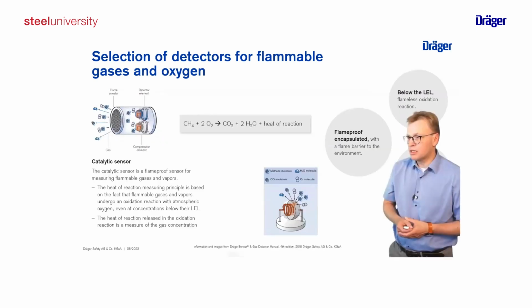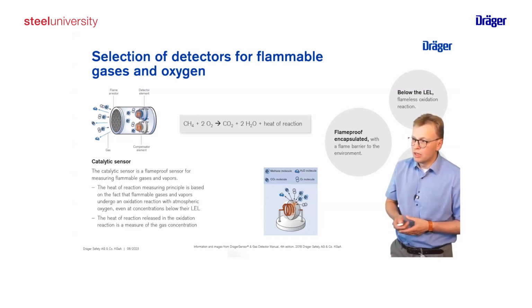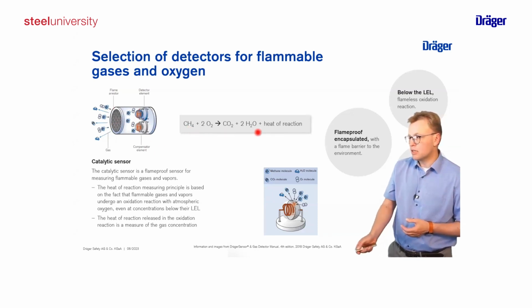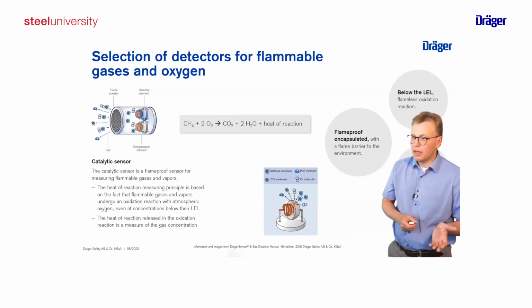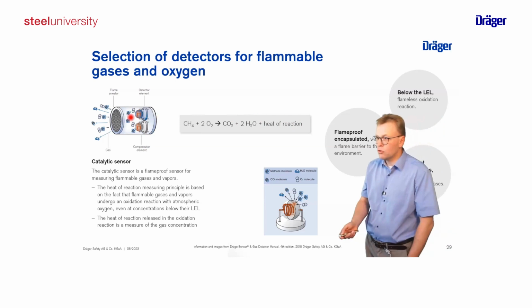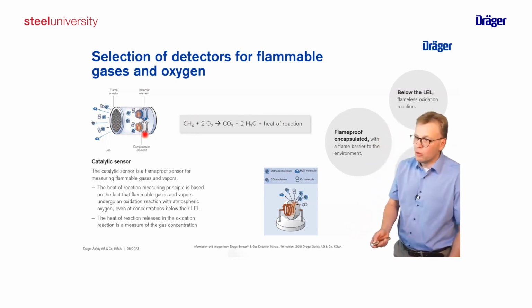The other principle, how we can detect gases, is the catalytic bead or catalytic sensor. We have again our gas molecules which vaporize, in this case, through a flame arrestor. We have an active, I would say, a hot wire. And what we do is an oxidation of, in this case, methane in this example, could also be hydrogen, with oxygen. We generate CO2, water, and one part is we have a heat of reaction. So we add energy, but as part of the combustion, we get additional energy. So the heat of reaction leads to an increase of the temperature of this wire, and this temperature increase is our direct proportional measure for the amount of gas which is inside.